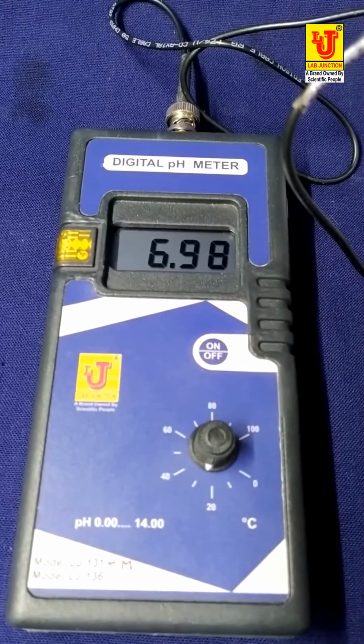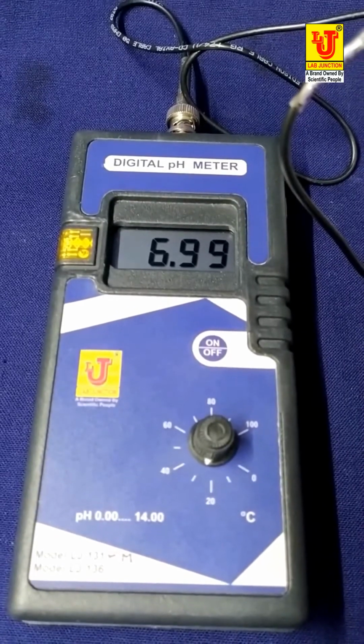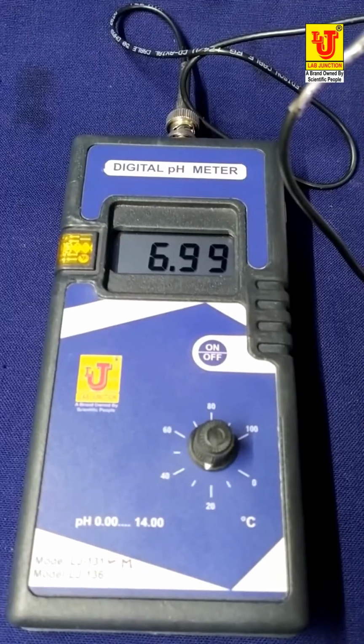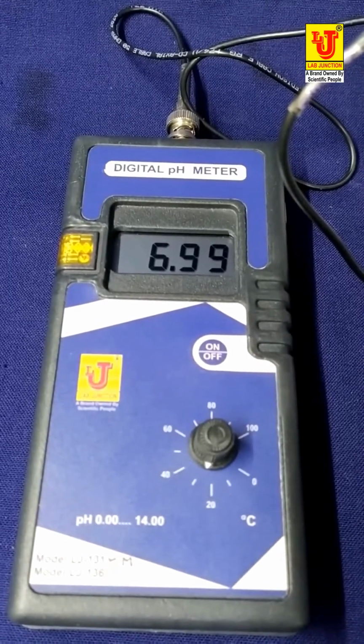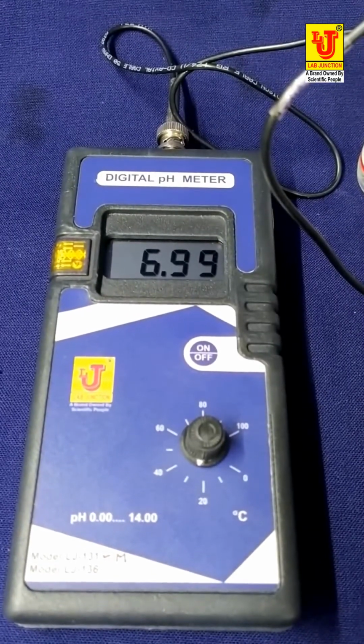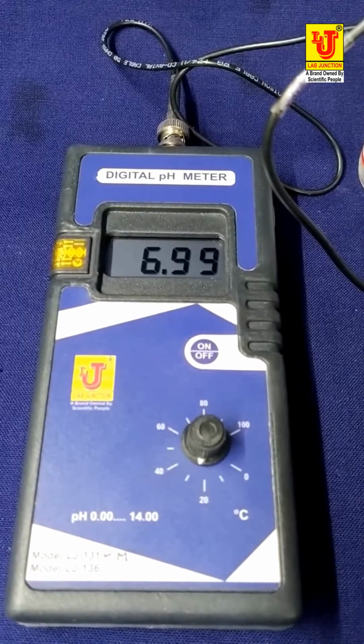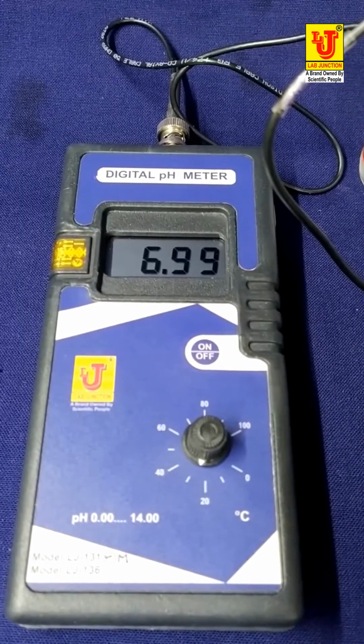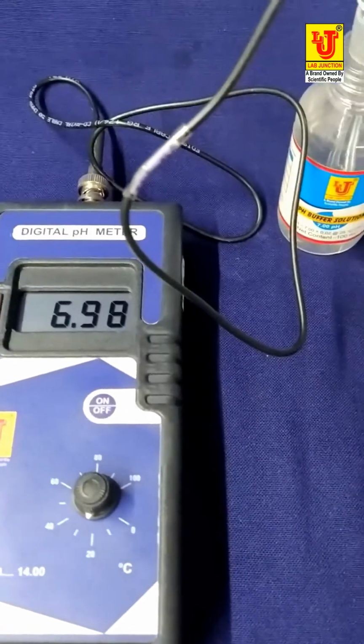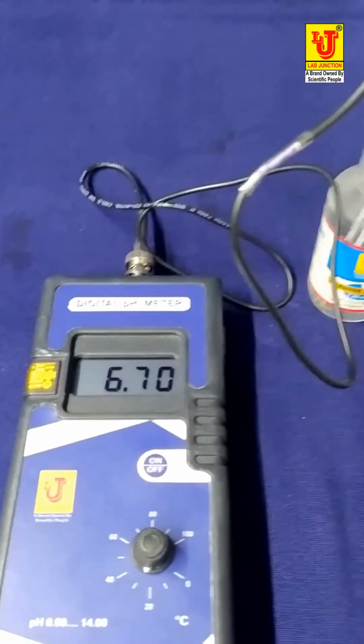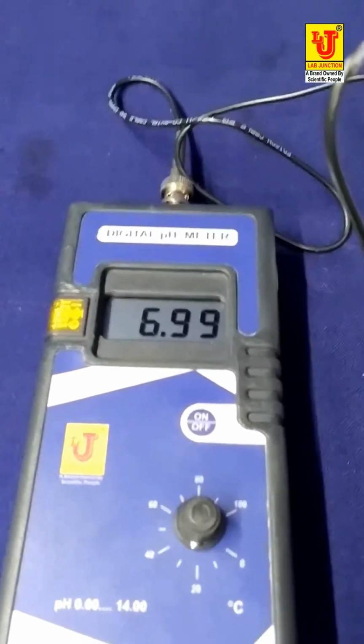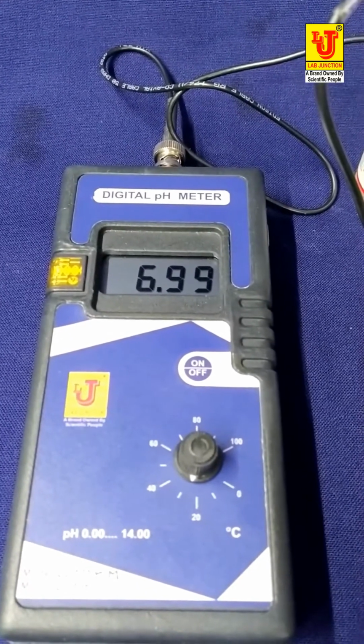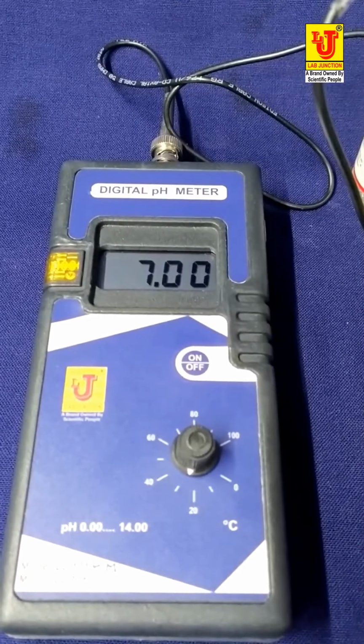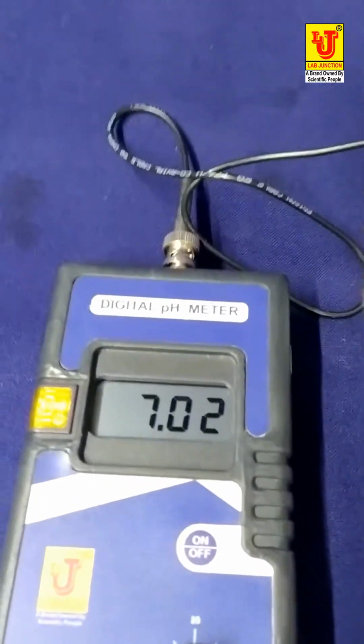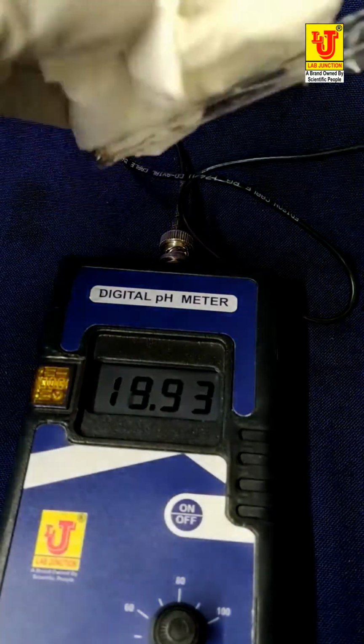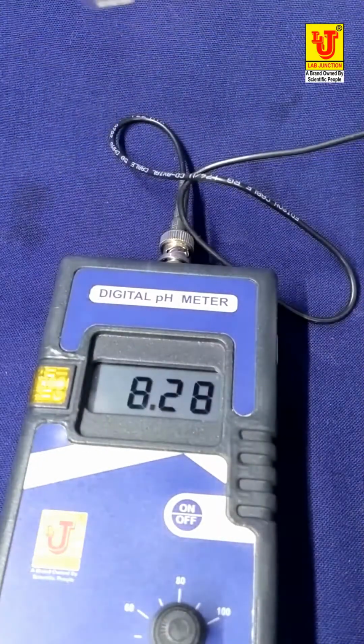Now I am reaching after calibration with the help of standard pH buffers 7 pH and 4 pH. Now please give time to reach up to 7 pH. For a fast result, please stir the pH electrode in the buffer. Now it reached up to 7. Now I am cross checking again. I am refreshing the pH electrode again with the help of tissue paper.